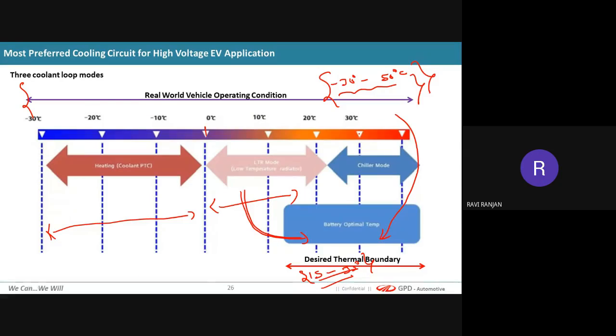Now coming to the high ambient condition, where we are operating more than 30 to 50 degrees Celsius. At that time, we cannot utilize the heat from the waste heat, because we have to go for the cooling mode. So at that time, we are providing a specific chiller mode. There, your electric compressor comes into picture, which is a quite power-consuming device. It consumes close to 2 to 3 kilowatts of energy during the chiller application mode. So it's huge energy, and if we are able to save that, close to 20 to 30% range will be improved if we are not loading the chiller of the battery system.